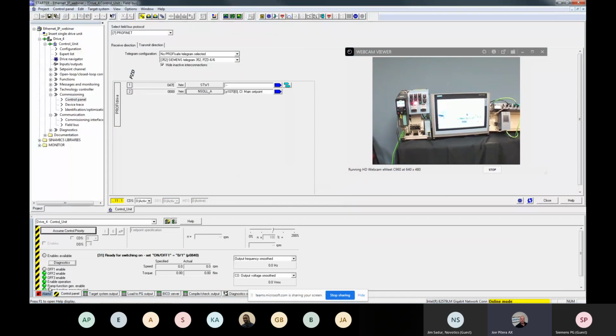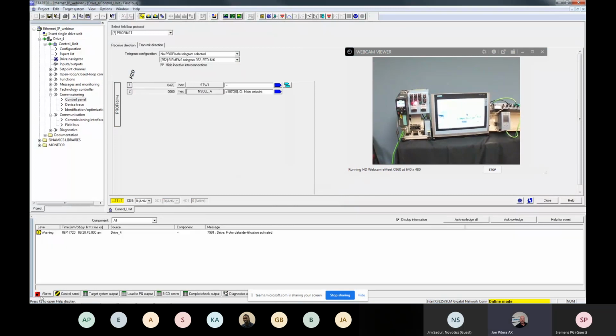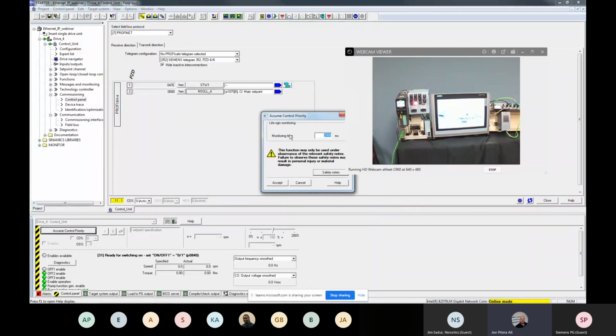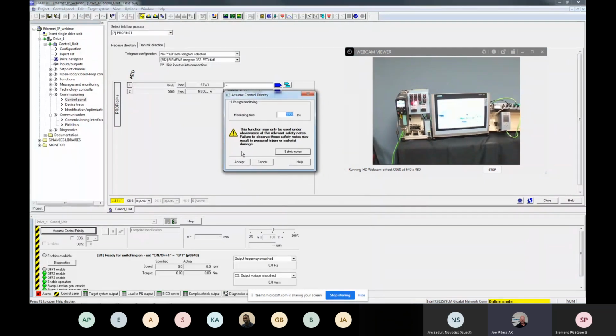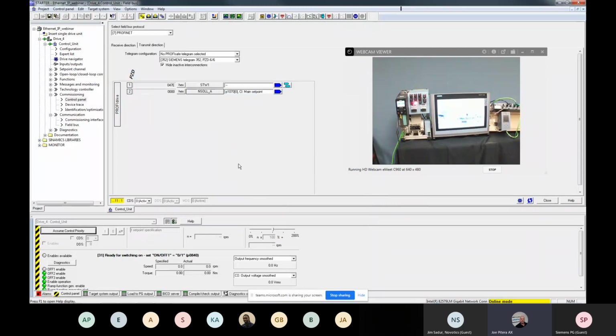At this point, a pop-up window shown on the bottom here has a few tabs. The one tab here is for alarms. The current alarm is a warning that the drive motor data identification is activated. We are going to assume control priority here, which gives us a little pop-up window saying that you are taking control of the application, so please be safe and make sure nobody gets hurt. This gives control now to my laptop, where I'm going to give it the enables, which now allows me to start the drive and give it an RPM. We do know that it's going to do a motor identification, so do not enter any motor RPM set point.